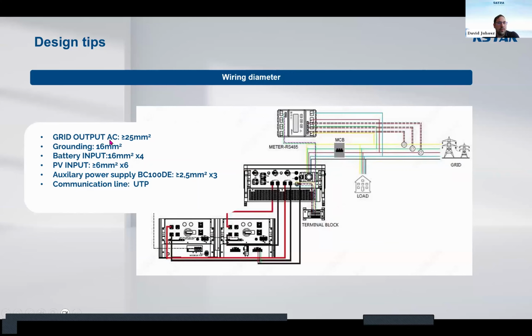There are some designing tips for the wiring. So the grid AC output needs to be at least 25 square millimeter, the cross section. The grounding needs to be 16 square millimeter. The battery needs to be 16 square millimeter 4 times, and the PV input is 6 square millimeter. The auxiliary power supply is 2.5 square millimeters 3 times, and the communication line is a UTP cable category 6.